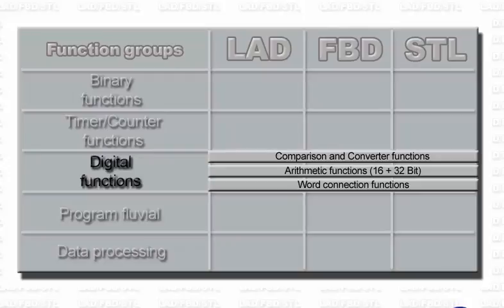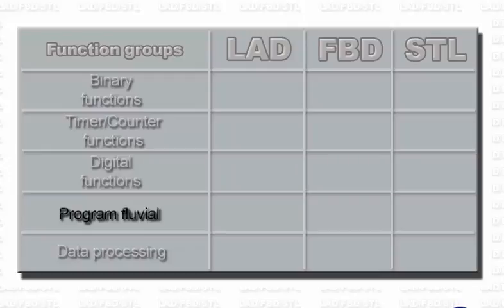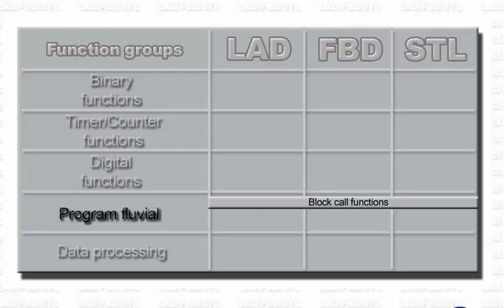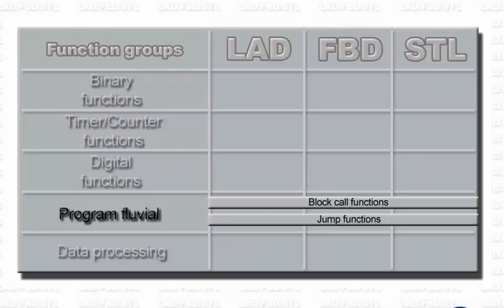The data formats used range from BCD-coded numbers to fixed point and floating point numbers. The next function group is a prerequisite for comfortable and well-structured program organization. Block calls are the most important aid for this. A block is a self-contained section of the user program — a sub-routine to all intents and purposes. By calling a block, you decide which program sections you want to process at a given moment. Within a block, the program flow is controlled by means of jump functions, which allow you to execute or skip certain program sections depending on the current result of logic operations.